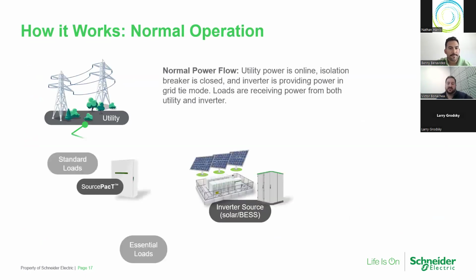Yeah, so let's go through a sequence of operation for an isolation device or SourcePacT. Usually you're going to have your utility system online most of the time, 99.999% of the time, your nines of reliability. And that's going to be feeding power to what, if you look at this one line here where the standard loads are connected, you can think of as your main board coming into a building.